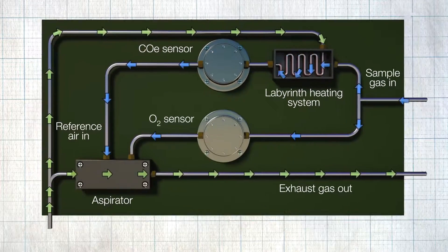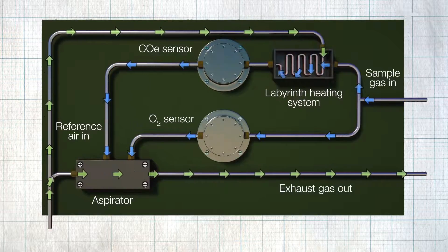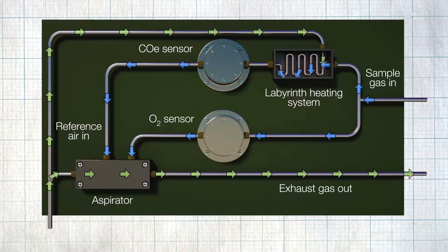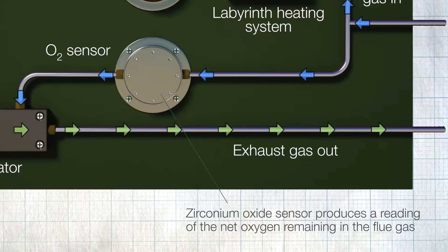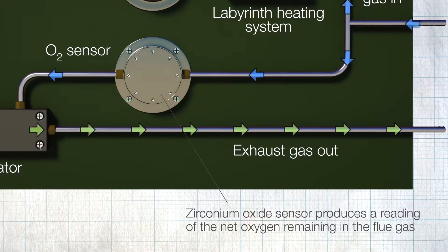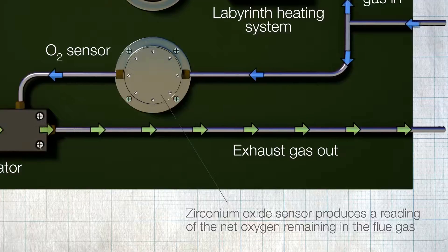Oxygen analysis is carried out by an industry standard zirconium oxide cell. Zirconium oxide sensor technology produces a reading of the net oxygen remaining after the combustion of all the available combustible gases.